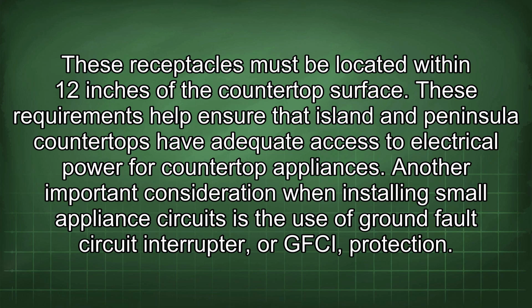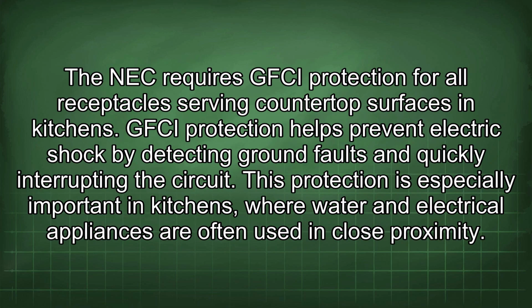Another important consideration when installing small appliance circuits is the use of ground fault circuit interrupter, or GFCI, protection. The NEC requires GFCI protection for all receptacles serving countertop surfaces in kitchens. GFCI protection helps prevent electric shock by detecting ground faults and quickly interrupting the circuit. This protection is especially important in kitchens where water and electrical appliances are often used in close proximity.